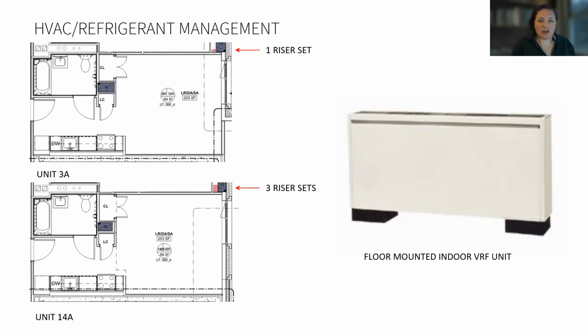Because of this building's tall height, we coordinated additional refrigerant risers to allow for a lower, middle, and upper zone in the system. This results in 6 risers at the upper floors, which reduce in number as the supply and return extends down the building. Cooper Park is incorporating a vertical distribution of refrigerant, as mentioned before when we walked through the plans. They're zoned per facade to provide comfort.